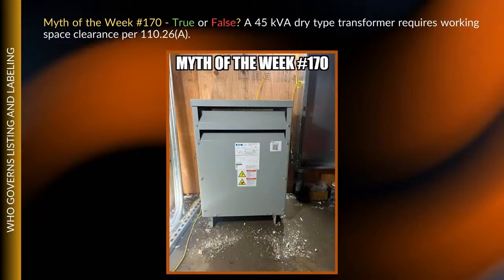So let's move on. Transformer — what's a transformer? Are we talking about a 5 MVA big green box out in the parking lot, or a doorbell transformer? It's not enough just to point and say, hey, disconnects need working space. What about the cord and plug connection under your sink for your disposer? Certainly that doesn't require 3 feet in front of it. So you've got to look at it on a case-by-case basis, equipment by equipment, site by site.